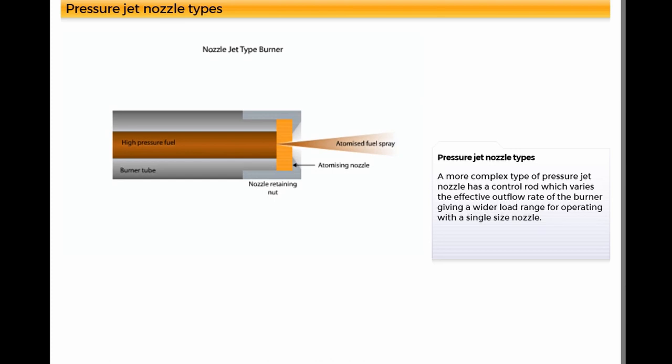A more complex type of pressure jet nozzle has a control rod, which varies the effective outflow rate of the burner, giving a wider load range for operating with a single-size nozzle.